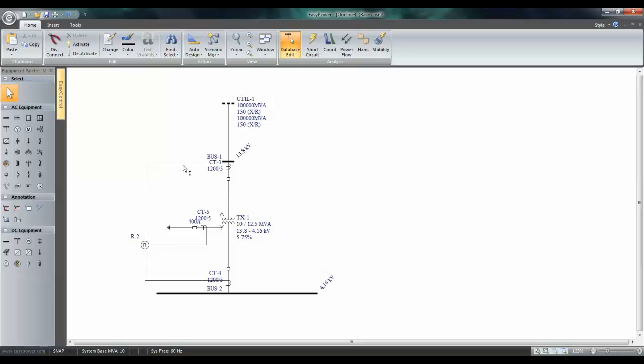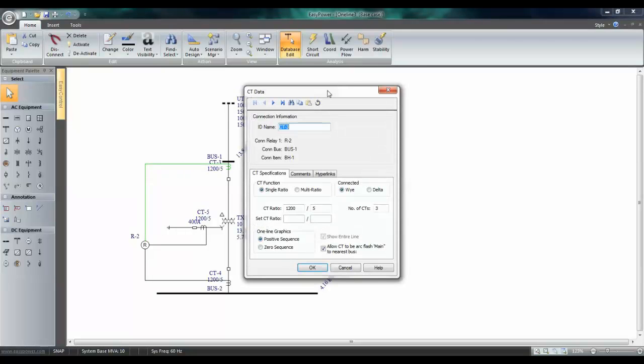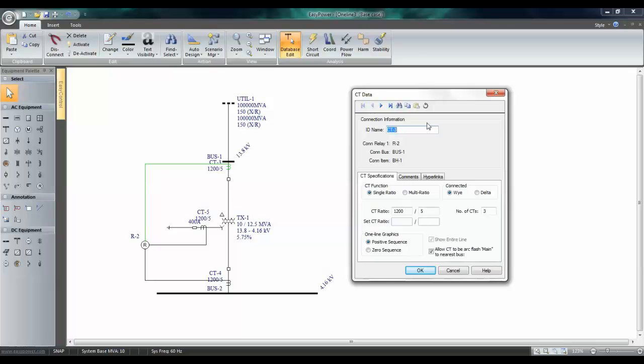Next, double-click on the CT to enter the ratings. This is a 12.5 MVA transformer at 13.8 kV. So, the full load amps is going to be close to 523.